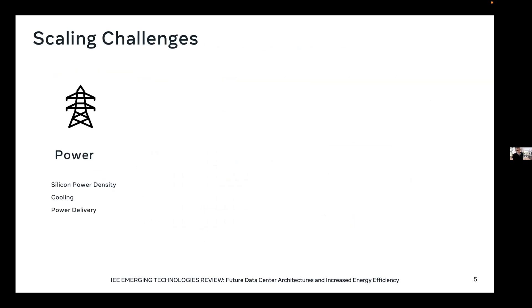So talking about some of the challenging scaling challenges — the first one I just mentioned was power. This is threefold. First, power in terms of silicon power density: with the end of Dennard scaling, even though we can build more and more dense logic devices, the problem is the power density of those logic devices is also increasing. That means eventually we're going to have to split those silicon elements up simply to deliver power to them and also to cool them. We also have an infrastructure power limit in terms of how much power we can get from the utility and deliver to a given data center, which bounds our ability in terms of power.